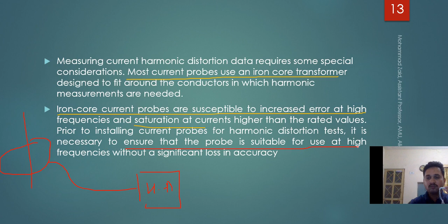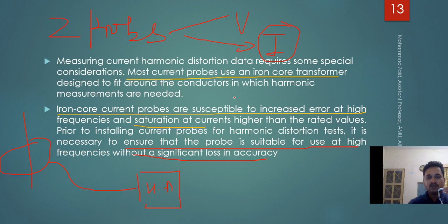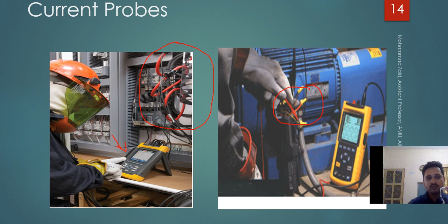There are two types of probes. One is voltage, another is current. At higher frequency, these current probes are more susceptible to error as compared to the voltage probes. These red things which you are seeing are all current probes, and this is your harmonic analyzer, and this is the panel in which your analysis is going to be done. These current probes are based on the Hall effect sensor, and are used for getting the current waveform directly in the analyzer, and they are made of iron, usually. So saturation can become a problem at higher frequency because of the BH curve.